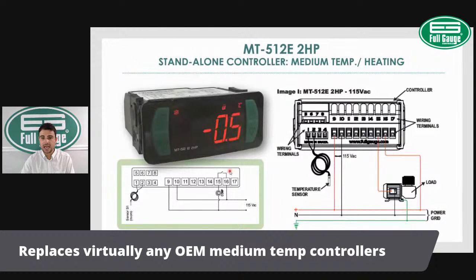So this is what we have in this wiring diagram: neutral into terminal 10 and the hot on terminal 11, sorry, terminal 9. So neutral going into terminal 10 and hot going into terminal 9. And that hot line is also going into my terminal 16 to feed power to the relay circuit. Once the relay closes, that power comes back in through terminal 15 and feeds my compressor. So this is a very simple, very practical example of how to wire the controller in 110, controlling a 110 compressor.